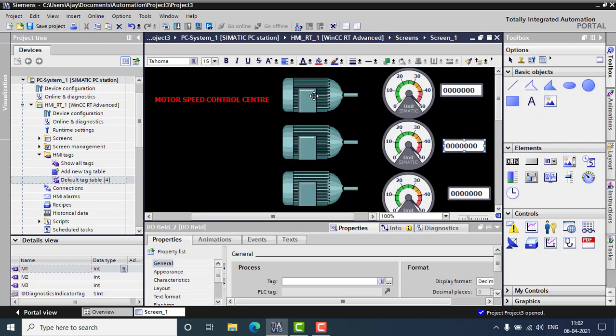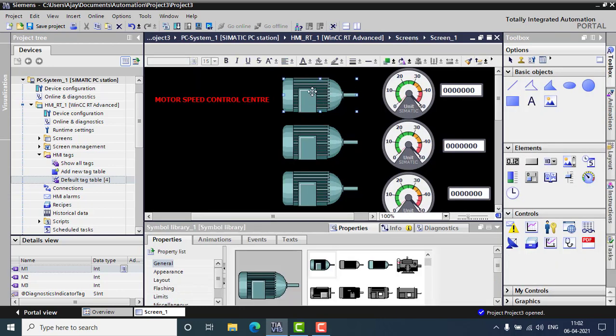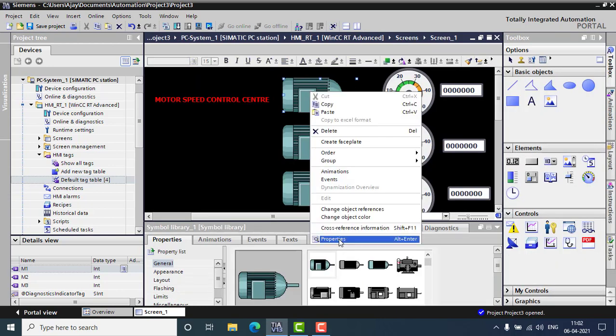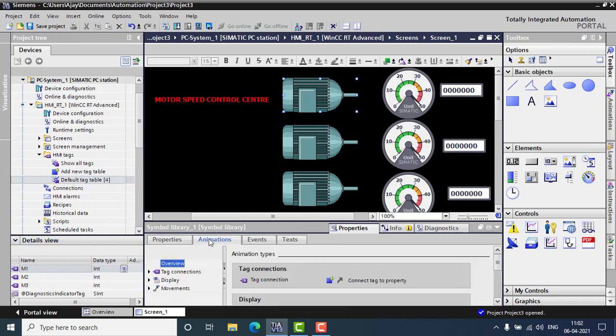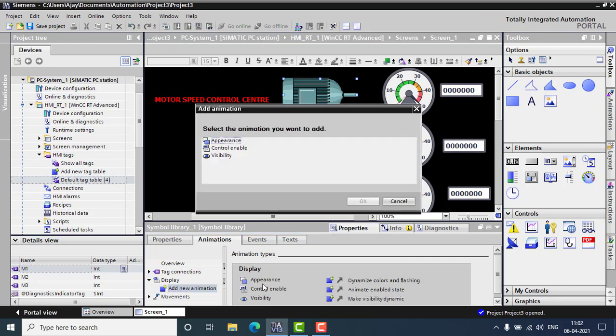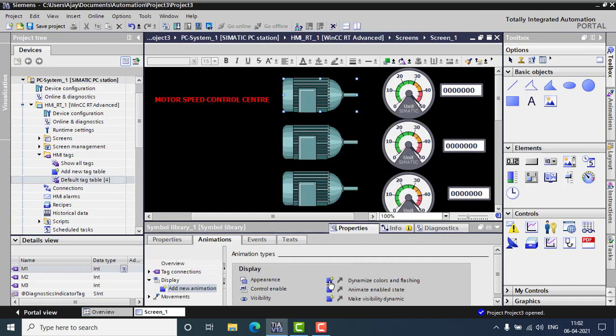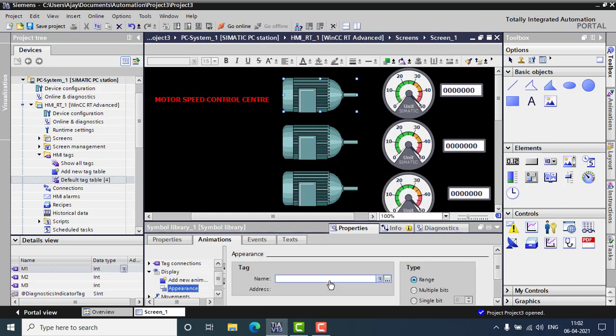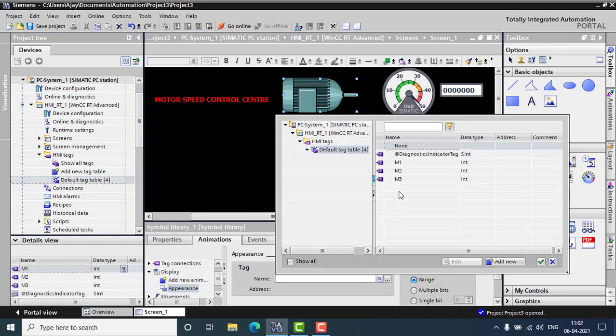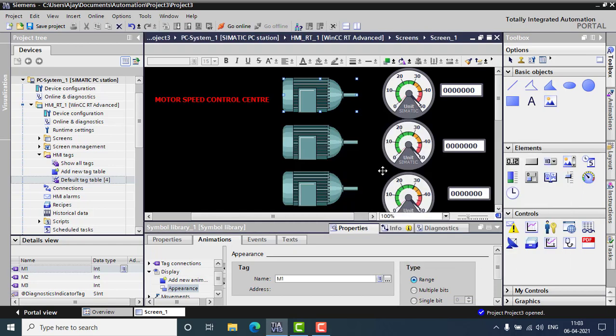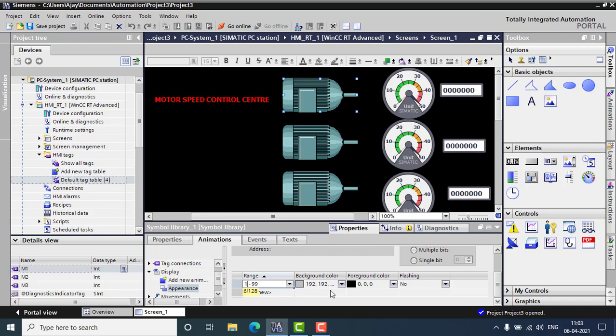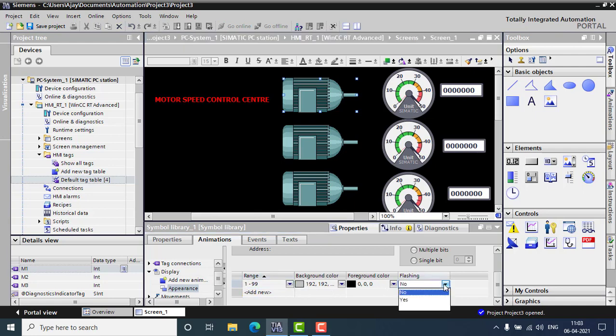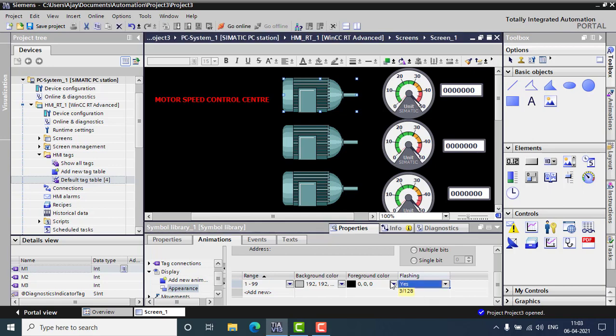So everything I can give in the motor. So right click and go for properties. In the animations, I can go for display. So in add a new animation, I just want to dynamize the colors and flashing. I just need to flash my motor when it is running. So I'm just giving the tag as M1. First motor is M1. So the range will be, I have to add range 0 to 99. I'm making it 1 to 99. When it is starting, the speed will be at least 1. So I just need to flash it. So I'm flashing it, yes.